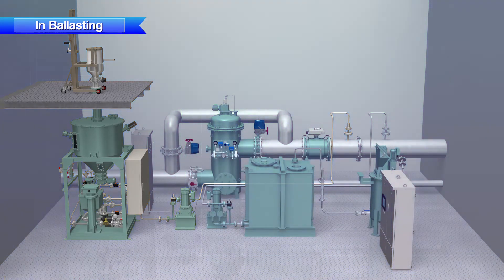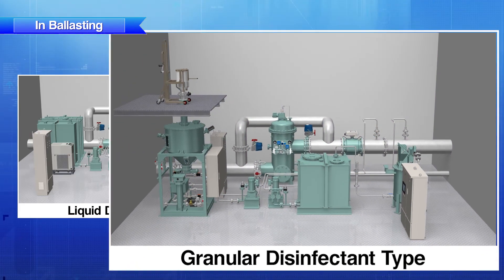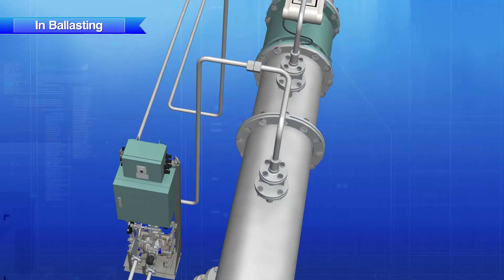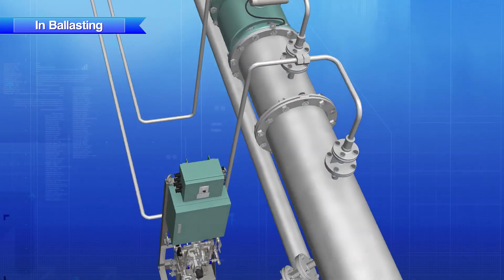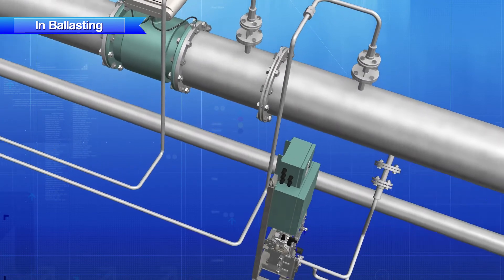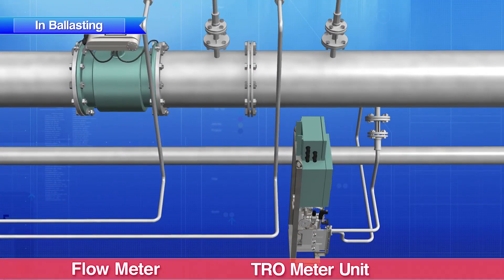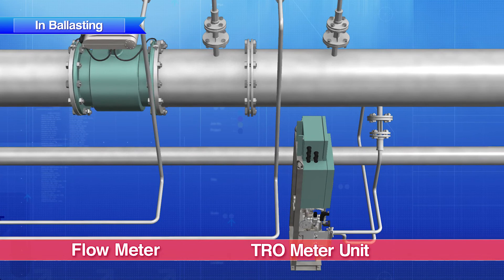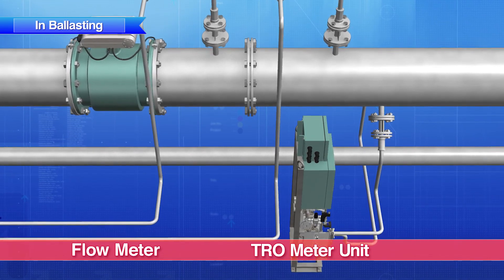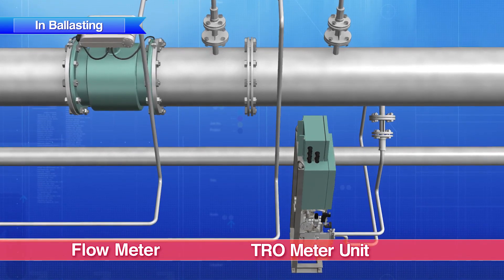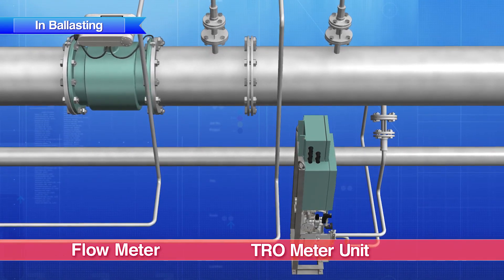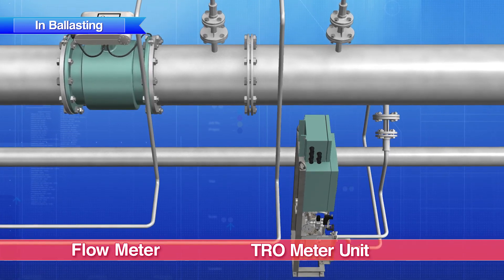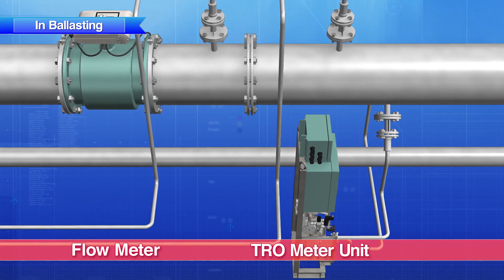Whether liquid or granular, the volume of disinfectant to be injected is calculated automatically based on data from the TRO meter unit and the flow meter. Just before the disinfectant is injected into the ballast tank, the residual chlorine concentration level is automatically adjusted to 2.5 ppm.